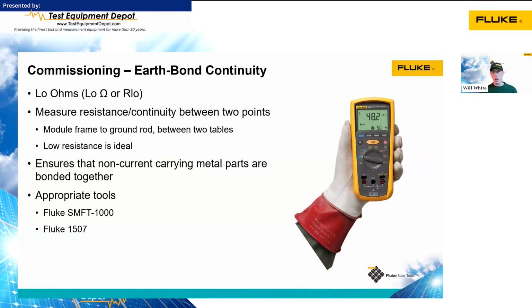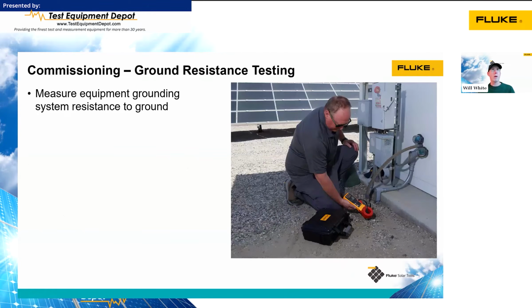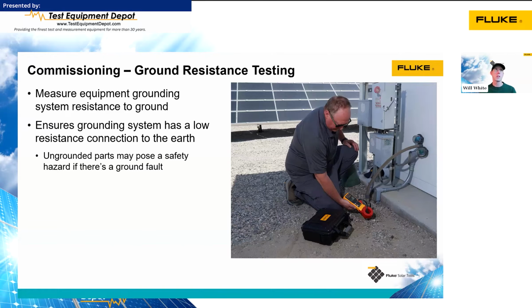The SMFT 1000 can do this earth ground bonding test, and the 1507 insulation meter can do it as well. They both test up to 200 milliamps, which is the requirement of an IEC standard for doing this type of testing. We can also do ground resistance testing at commissioning, and it's somewhat similar to the earth bond grounding measurement, but in this case, we're checking to make sure that the ground rod actually has a really good connection to the physical earth. So again, looking for low resistance there.